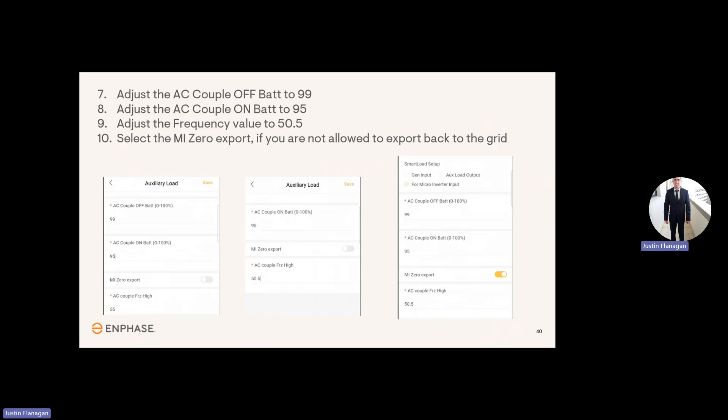Next, you'll adjust the AC couple off battery to 99%. Adjust the AC couple on battery to 95%. Adjust the frequency value to 50.5 Hertz. Select the MI0 export if you're not allowed to export back to the grid.